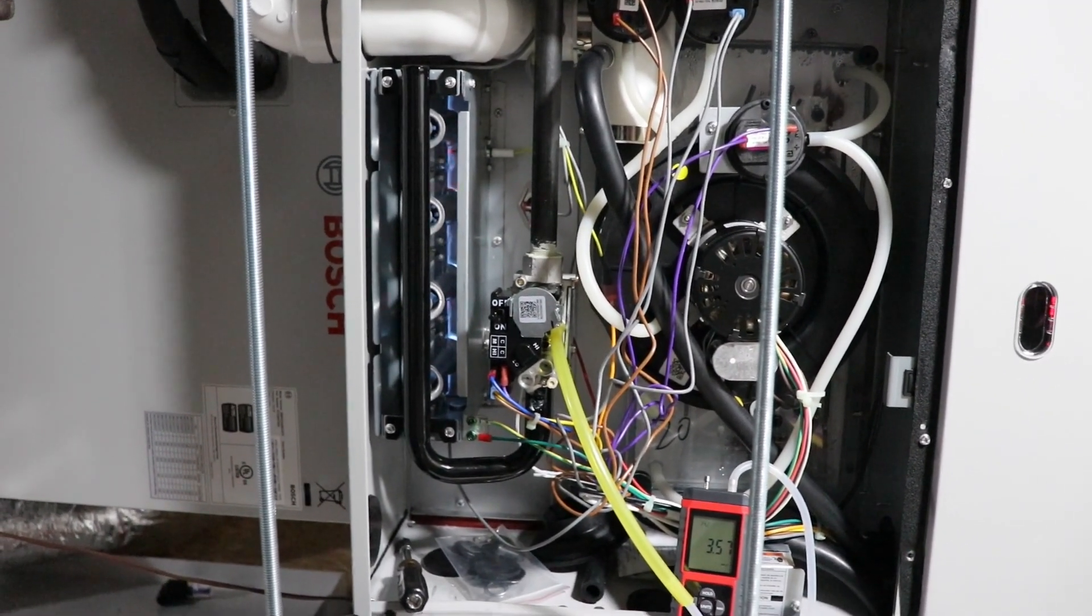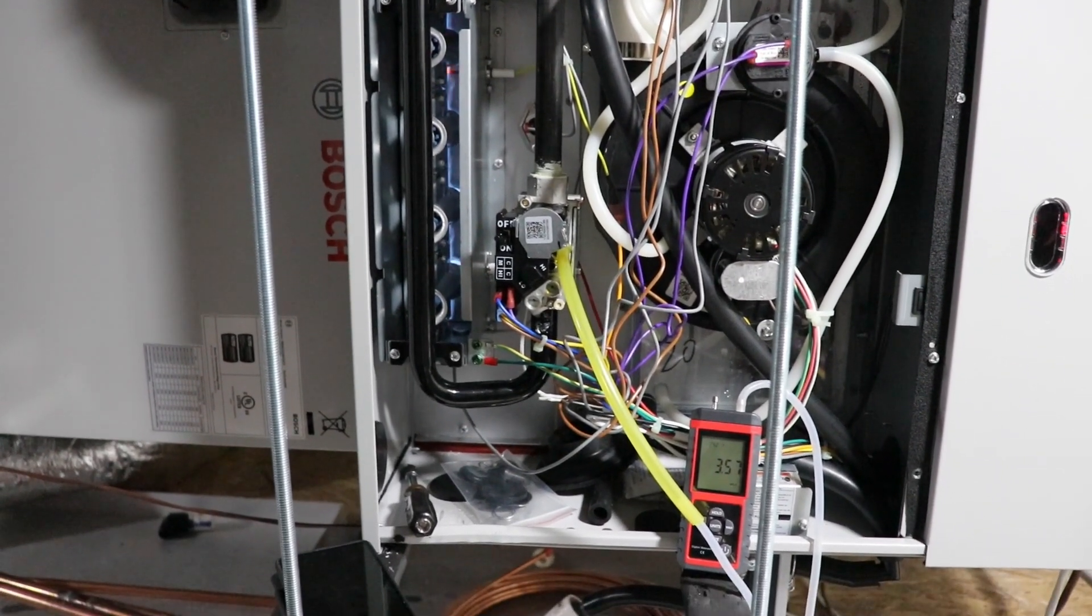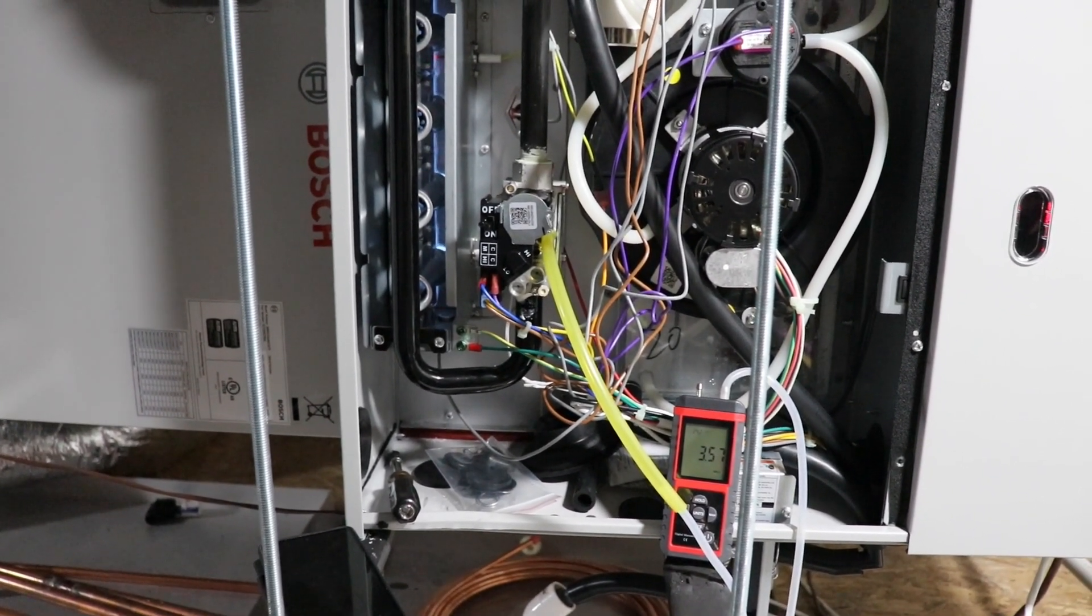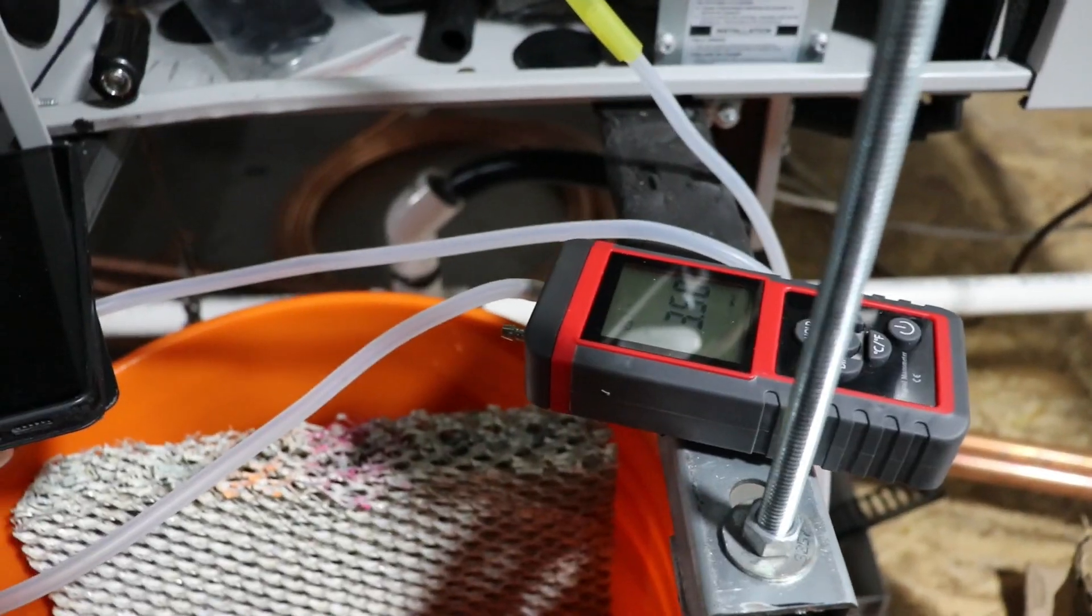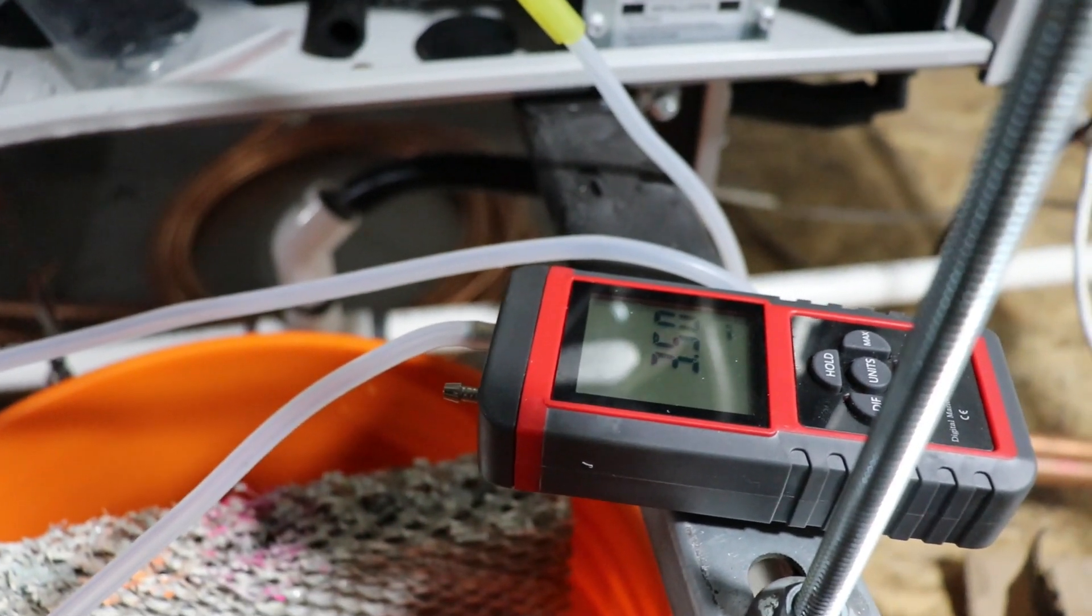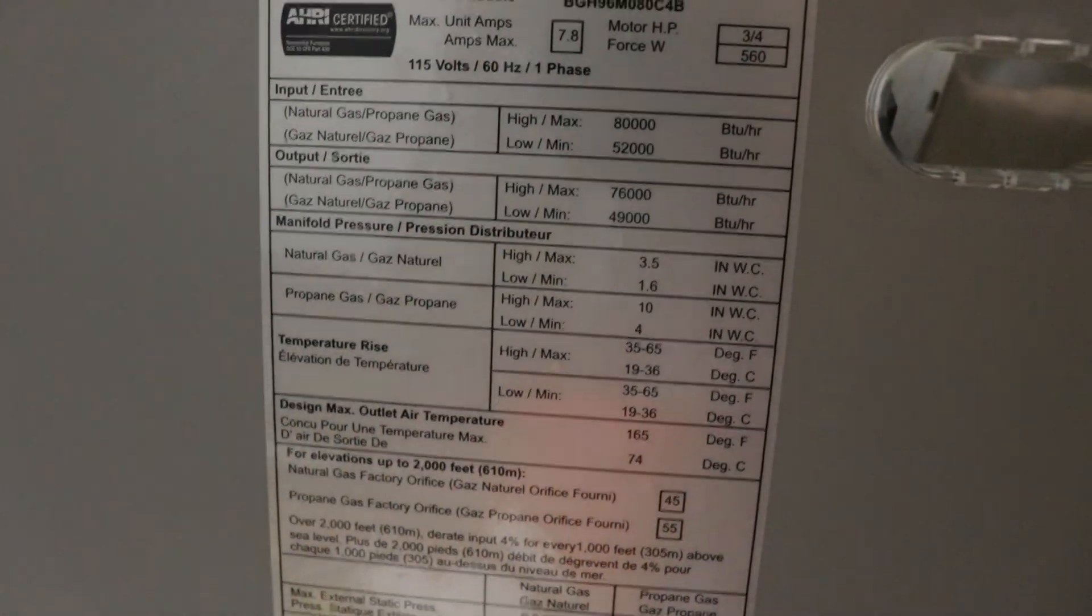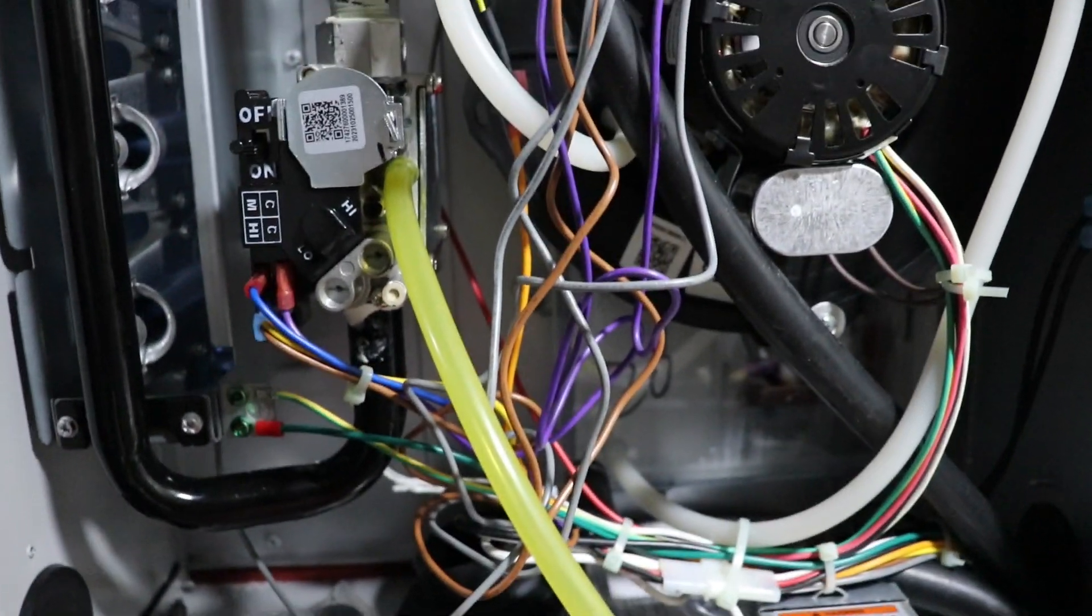I'm going to have to sit here for the next half an hour to an hour and make sure that we can get full heat out of this thing. I've got the sensor set to 3.5 here. I think I might have been at 3.6 previously. I kind of somehow muddled the two numbers together between 1.6 and 3.5.